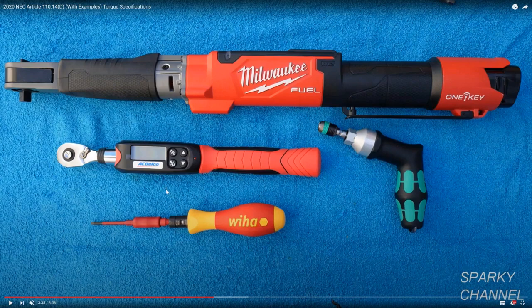Now, somebody says very difficult to use tools on site in case of maintenance. Well, the thing is you can get the analog version without a digital screen. So if that's your worry, you can get a torque wrench without a screen. That's not a problem. The screwdriver is not battery powered. So you can get the torque wrenches that you need. So your terminals won't be too tight. You won't damage any cores. They won't be too loose. Your studs won't break, whether it's a high voltage stud or a motor stud.